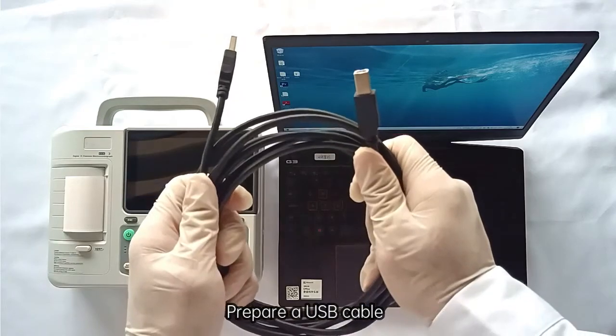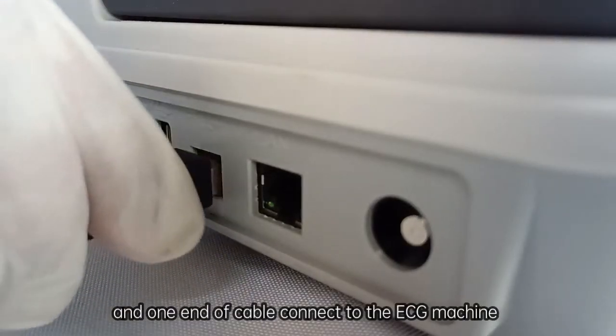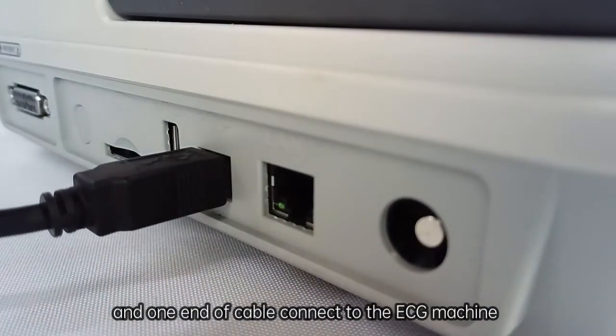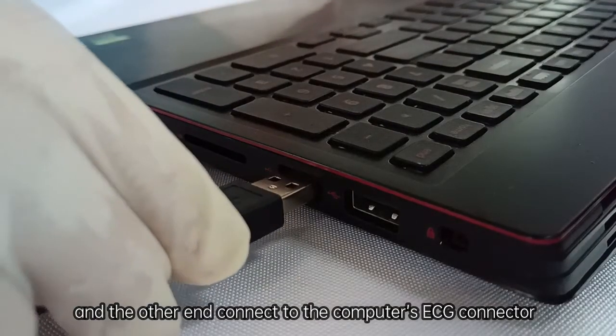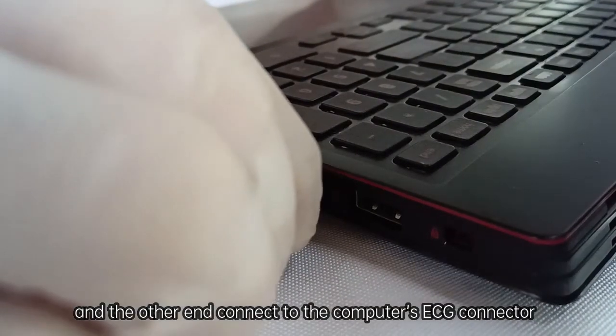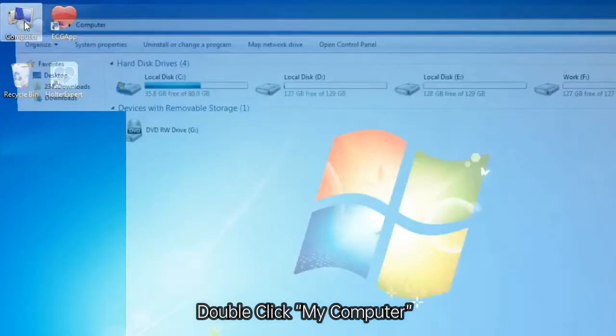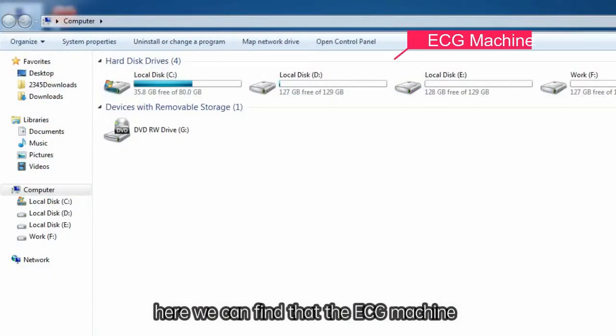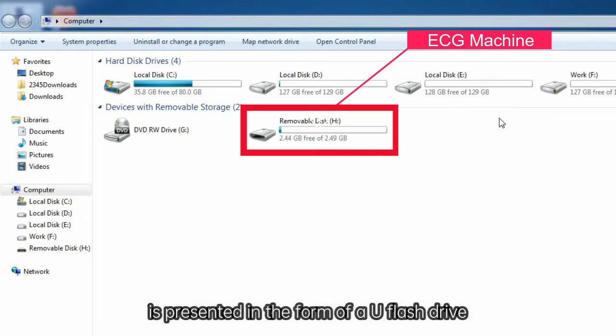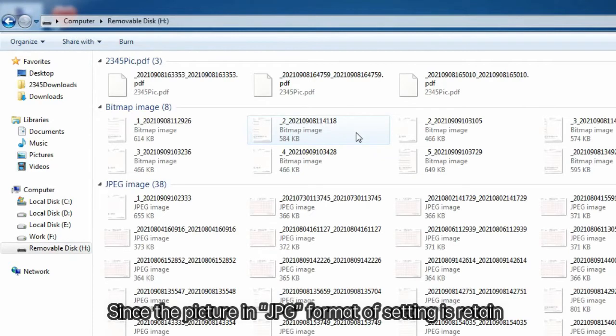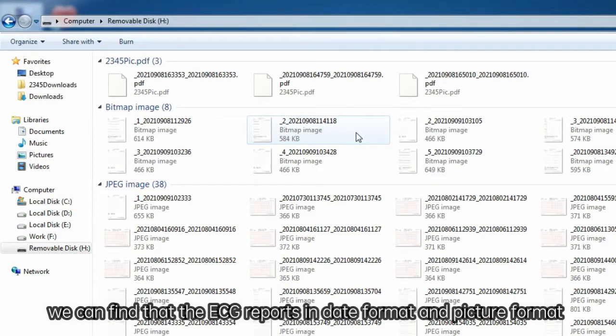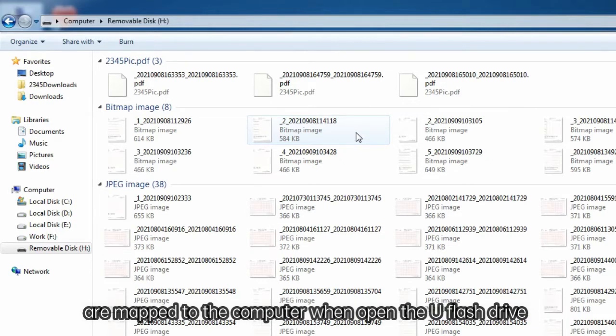Prepare a USB cable and connect one end of the cable to the ECG machine and the other end to the computer. Double-click My Computer. Here we can find that the ECG machine is presented in the form of a U flash drive. Since the JPG picture format setting is retained, we can find that the ECG reports in data format and picture format are mapped to the computer when opening the U flash drive.